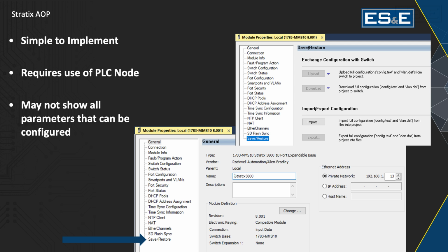So what do you think the downside of doing it this way is? It takes a connection in the PLC. That's the downside. And most customers, that's usually not an issue, but believe it or not, I do have some customers that it is an issue. And so even though some of these controllers can support up to 500 nodes or devices configured there in the tree, they are exceeding that, and it's becoming an issue for them. And so that's probably the biggest downside to doing that, other than managing firmware and ensuring the firmware matches and stuff like that as you have that configured in the controller. So some things do need to match. That would be the only caveat that I would say about adding it into the controller project.